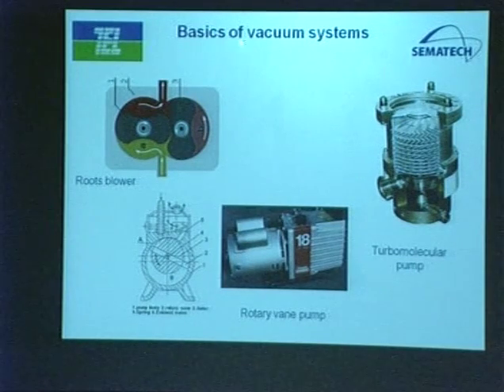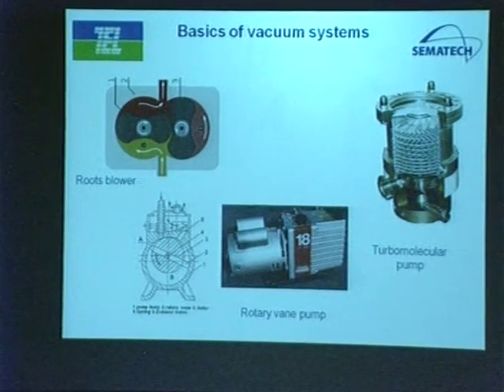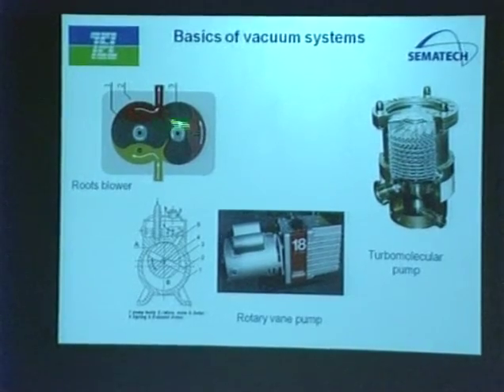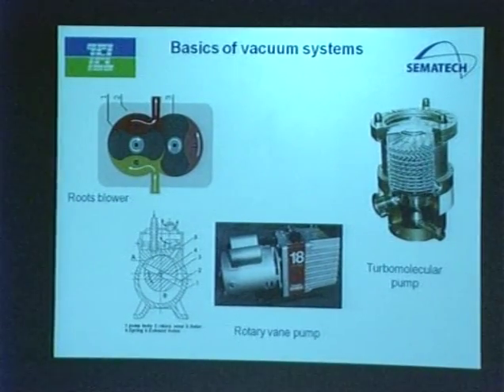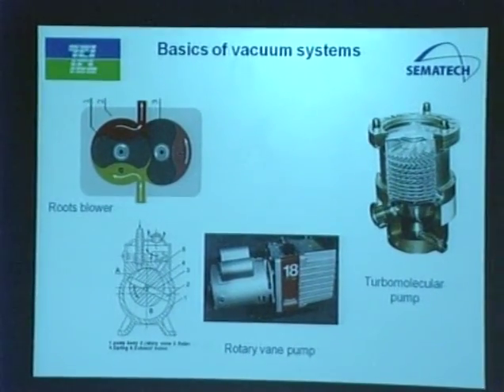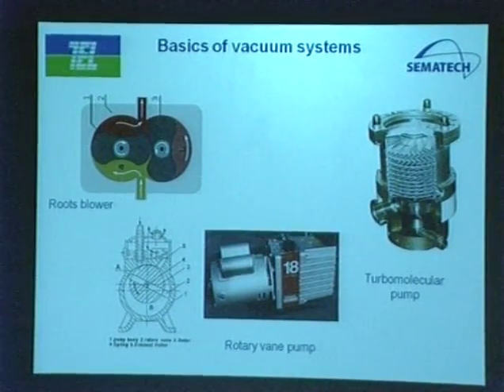The basic vacuum systems used on most every plasma system, whether it's deposition or etch, have a roots blower, which is nothing — I look at it as just a big fan. It blows large volumes of gas, it can handle lots and lots of gas, but it doesn't really pump to a very low pressure. That's why you have a roots blower that sets on top of what's a very common pump in the industry, these rotary vane systems. So you've got this system, which will actually get you to a millitorr level of pressure.